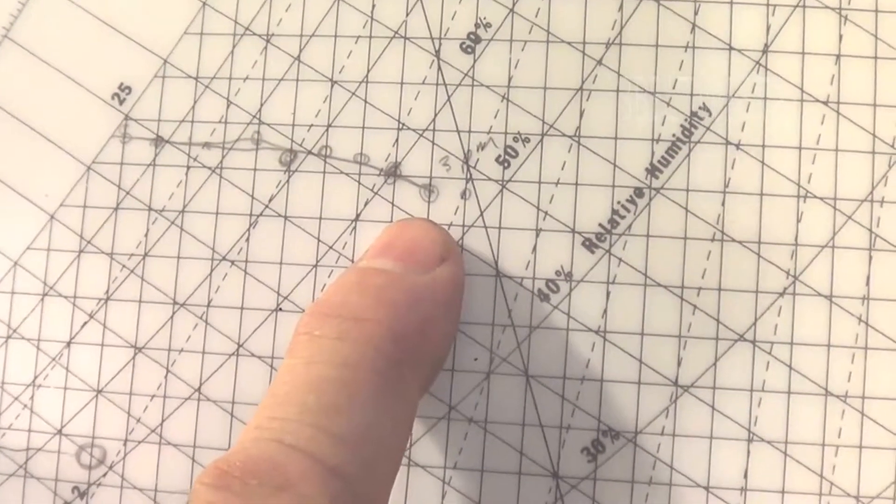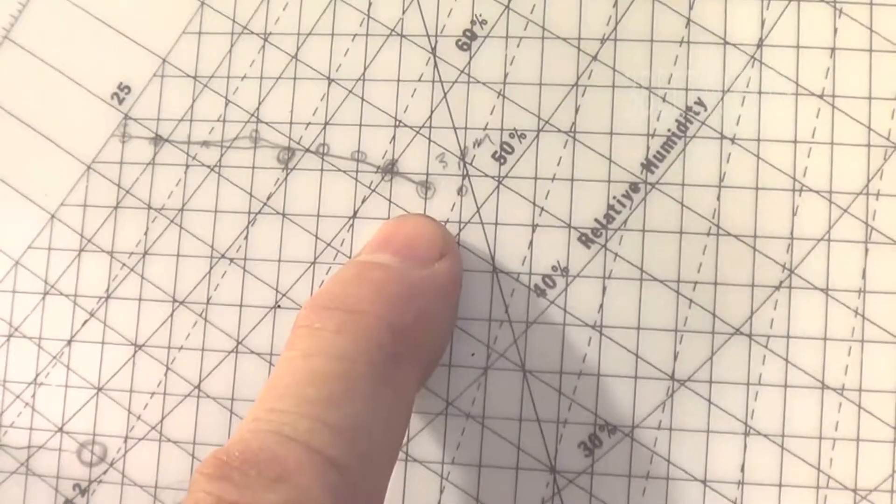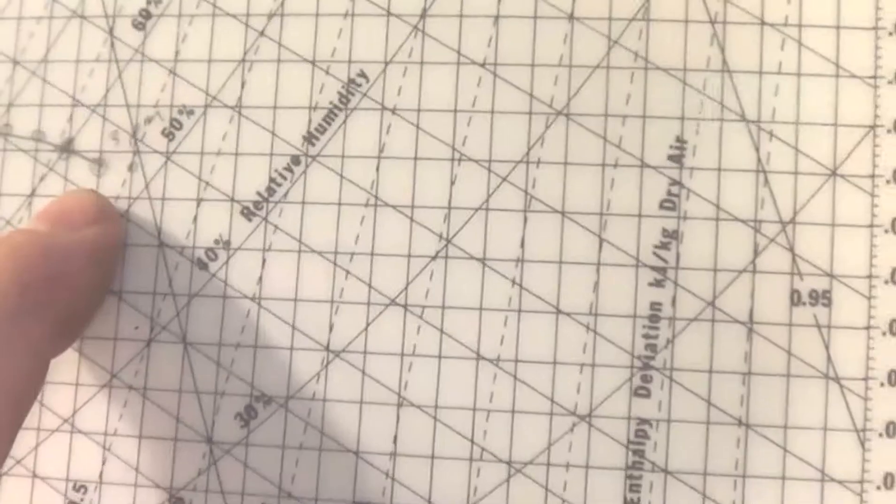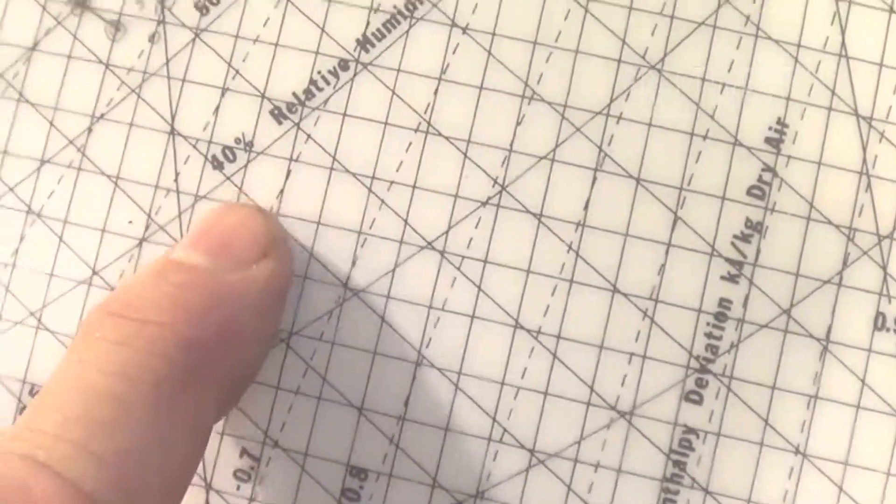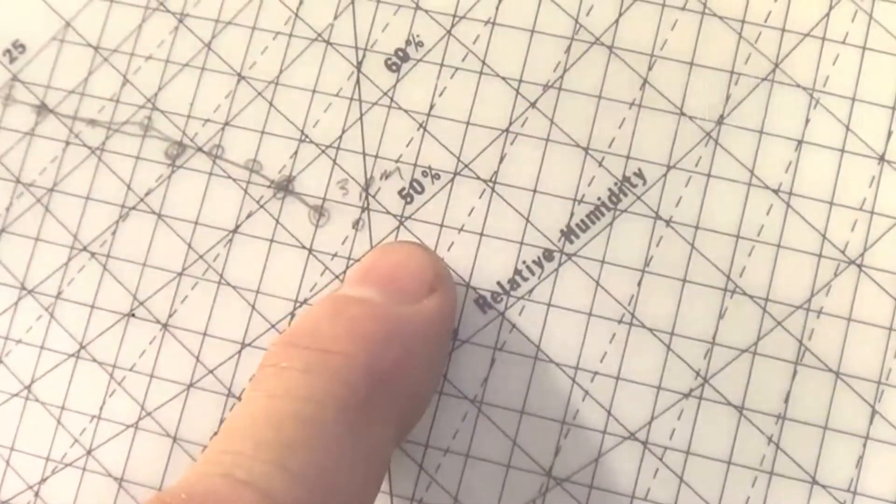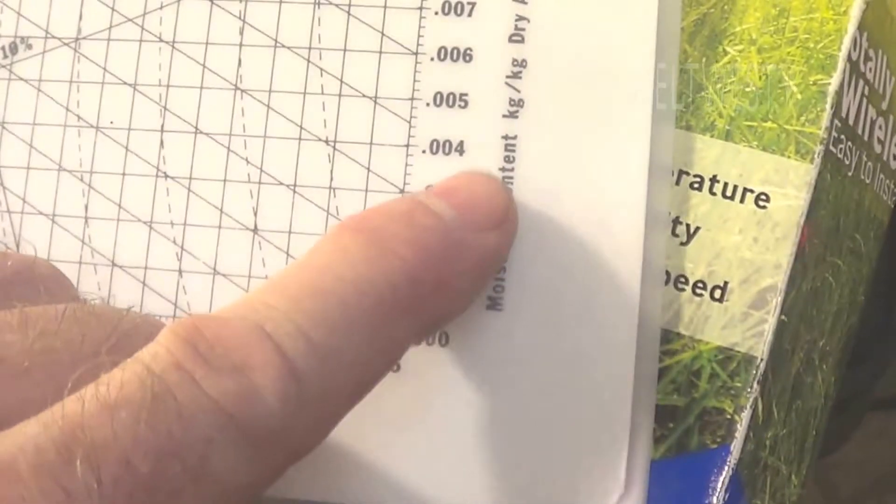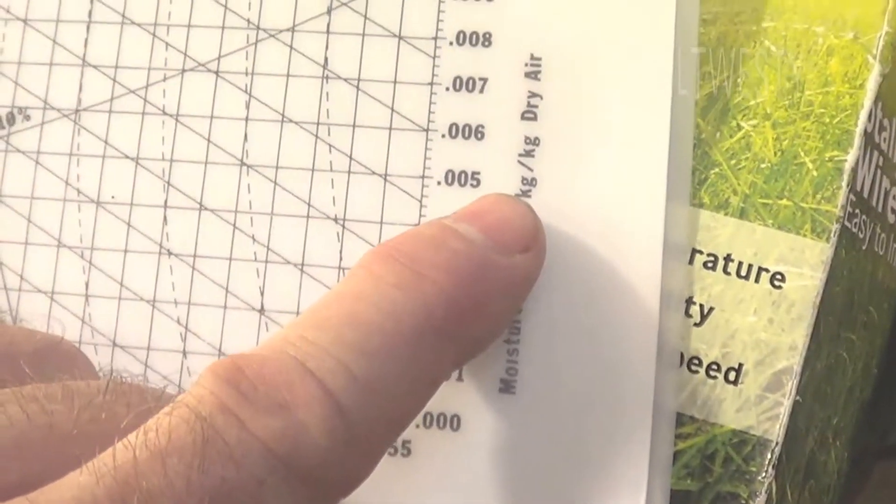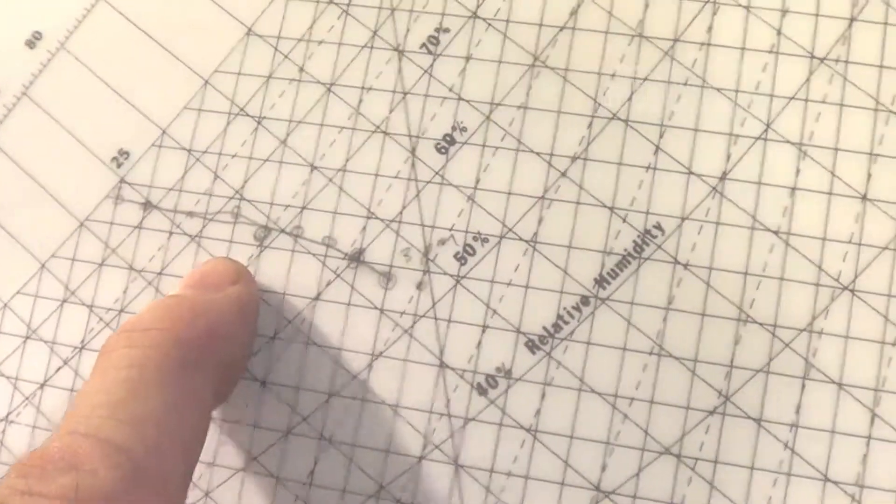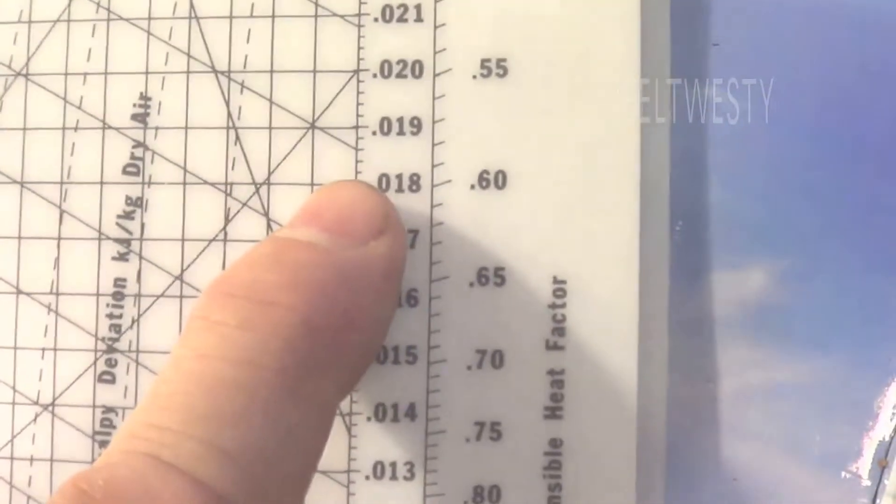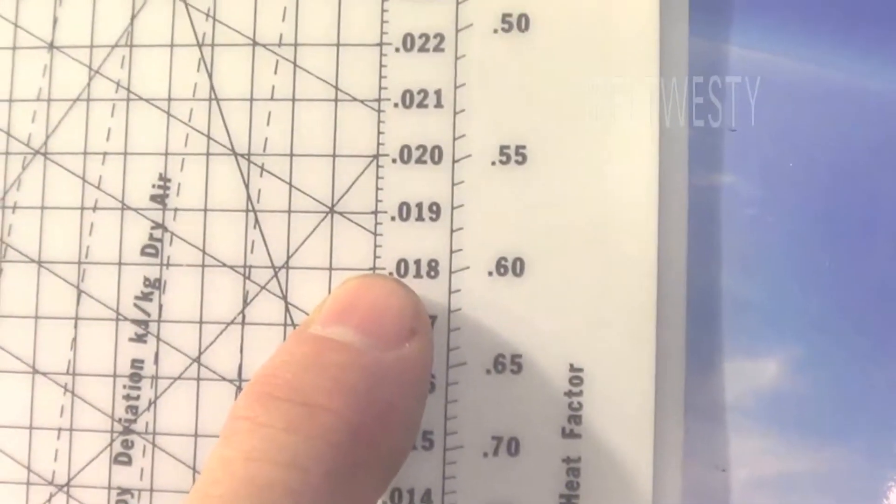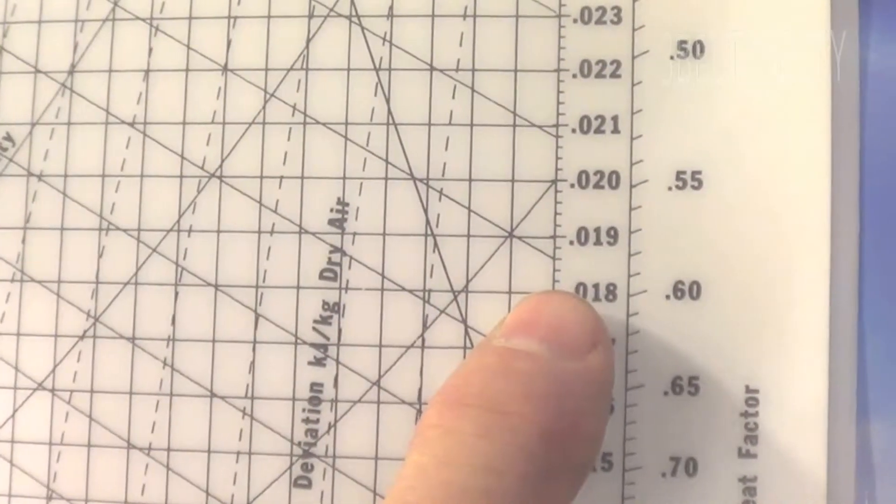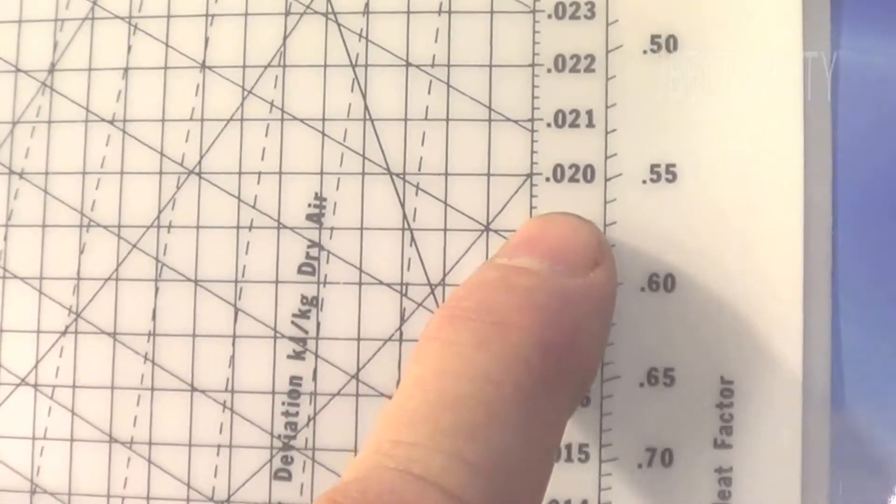And then at the peak it was hot, 35 C, 54 percent humidity. That's relative humidity. This line here is a 50 percent line, that's a 60 percent. And on the metric chart this has got moisture content of kilograms per kilograms dry air. So we've got over here point oh one nine.